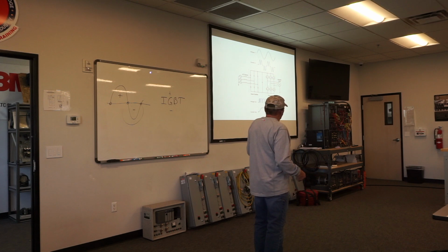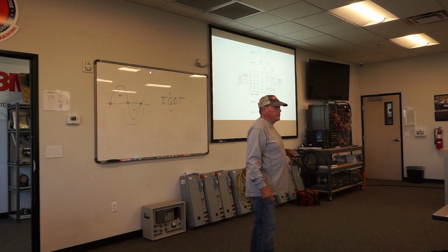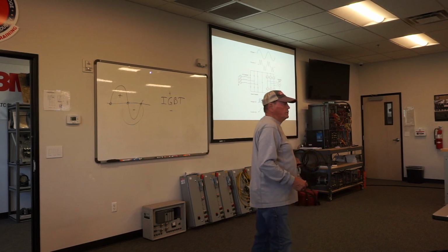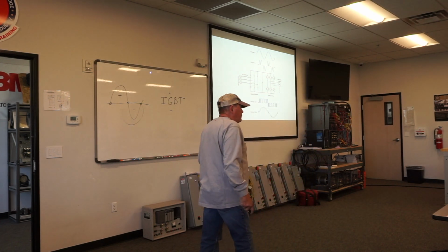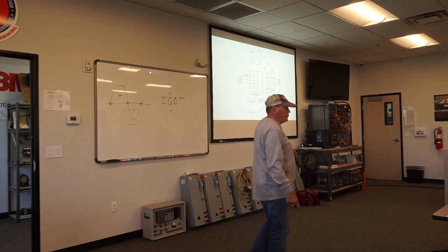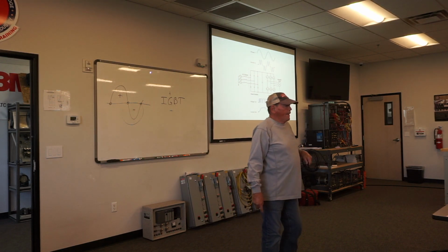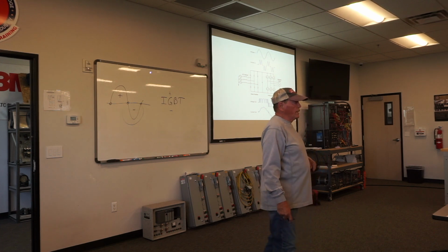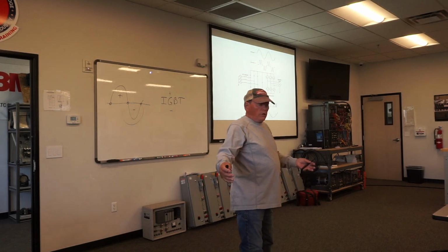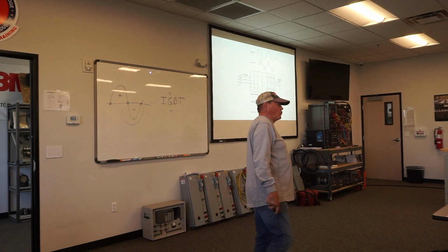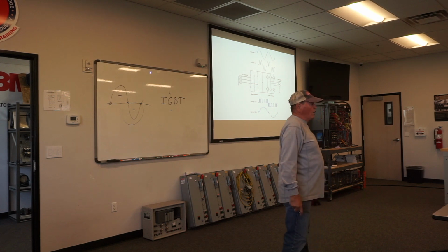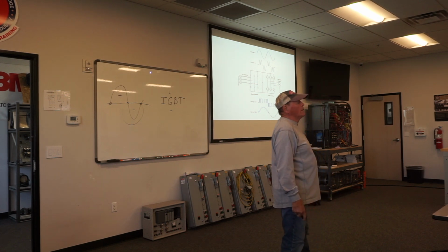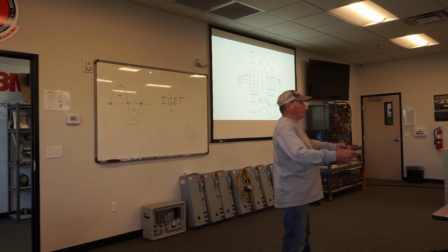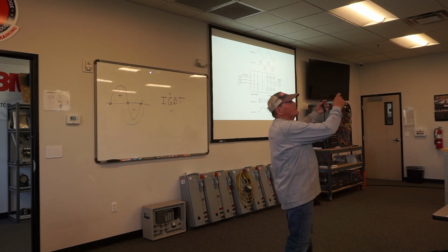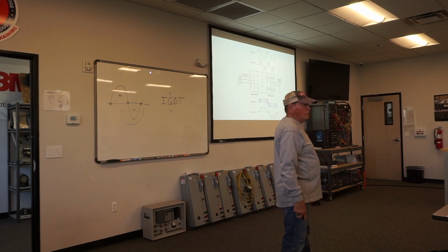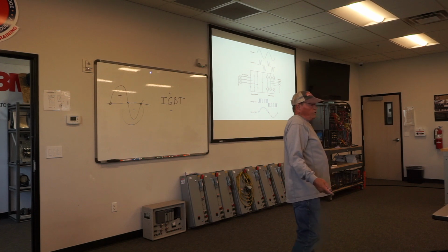These IGBTs will blow up, and I've replaced a lot of them in solar inverters. Same component is in a solar inverter as in a variable speed drive. And I just worked on one this morning out at the Golden Eagle Park. I got the blown up parts in the back of my truck. I had to disassemble this morning to see what was blown, because while I was working on it, the sucker blew up. Oh my gosh. And pretty soon all this black smoke started flowing out of this inverter. Oh crap. Now I got to tear the sucker apart and see what went. But they're 12 years old. They've lived their life.